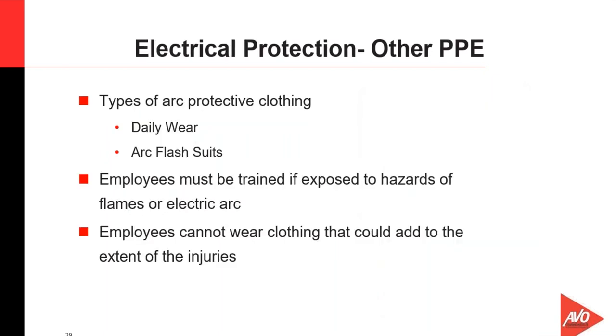We have other protective items. The daily wear and arc flash suits are very common today in electrical work. Employees have to be trained in the hazards associated with flames or electric arcs. They have to be trained in the levels of protection that they would have available to them, how to use it, and then overall how to mitigate the issues of electric arcs and arc flashes. Employees are prohibited from wearing clothing that, if ignited by an electrical arc, could continue to burn or could cause further injury. And that is a direct 1910-269 OSHA requirement.